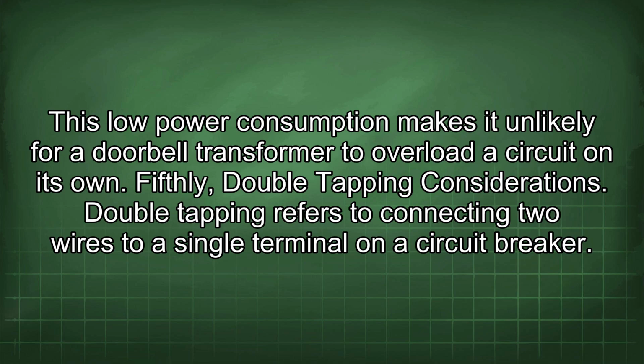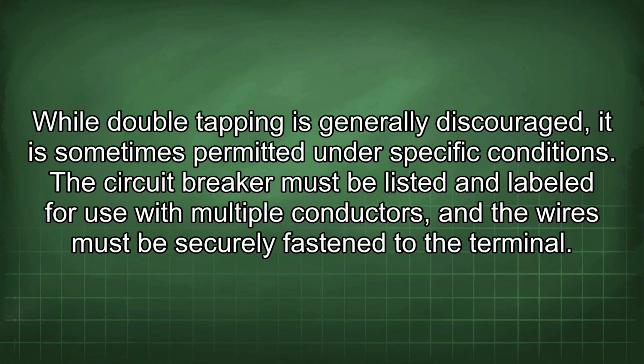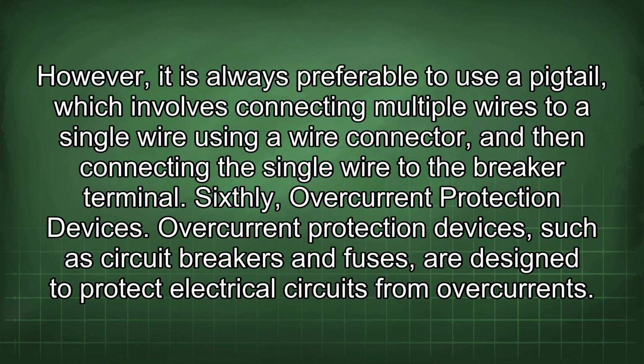Fifthly, double tapping considerations. Double tapping refers to connecting two wires to a single terminal on a circuit breaker. While double tapping is generally discouraged, it is sometimes permitted under specific conditions. The circuit breaker must be listed and labeled for use with multiple conductors, and the wires must be securely fastened to the terminal. However, it is always preferable to use a pigtail, which involves connecting multiple wires to a single wire using a wire connector, and then connecting the single wire to the breaker terminal.